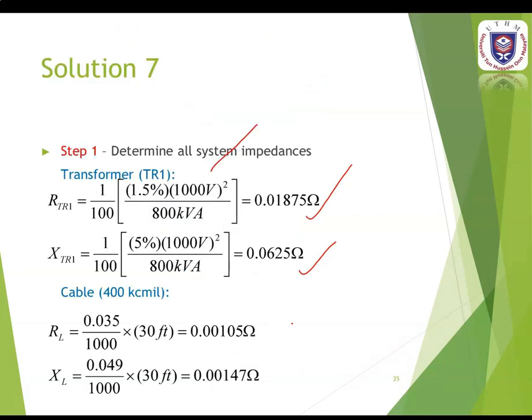You insert the value from the table and you get the resistance as 0.00105 ohms and the reactance as 0.00147 ohms. Next is the cable for the 8 AWG. You refer to the 600 volt table to identify the resistance and reactance values for the 8 AWG cable.